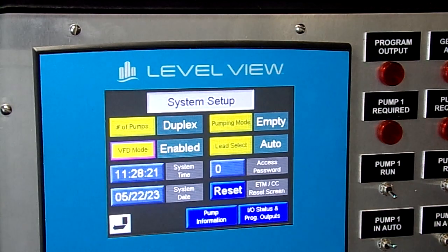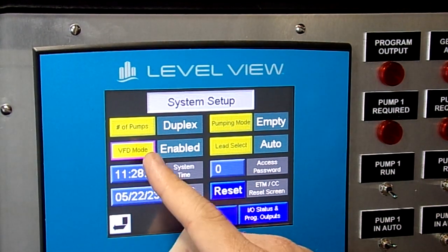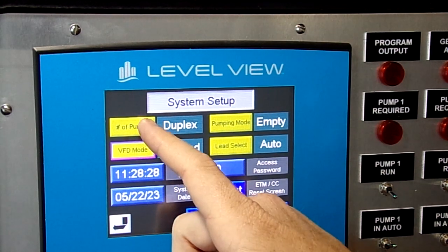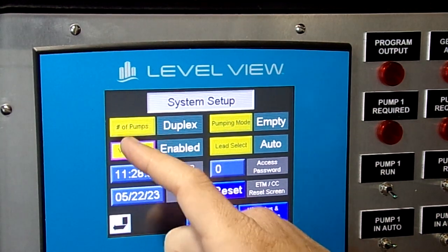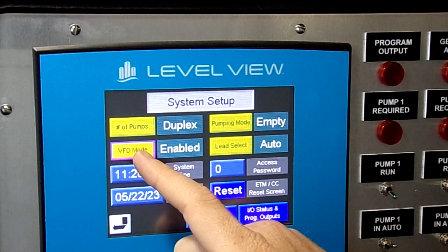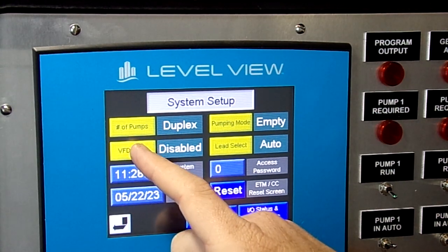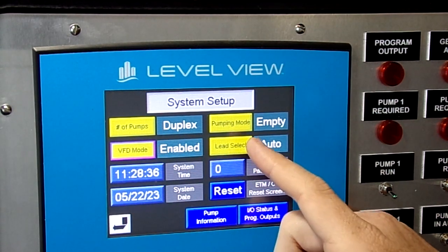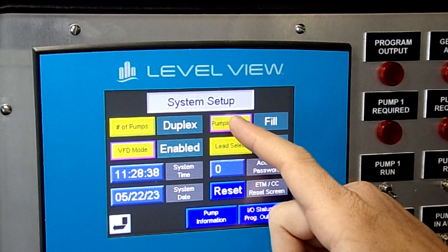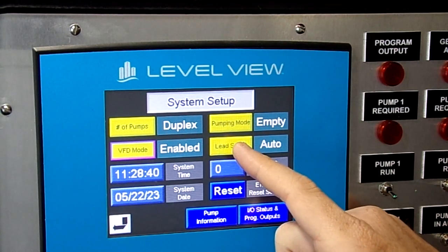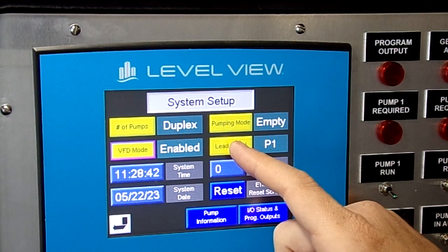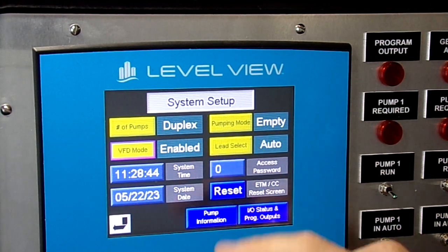The system has a multitude of different applications that it can be run for. So we have a duplex or a triplex. We also currently have this set up for VFDs that can be disabled or enabled. This station can be set up to empty or fill stations. And then we also have the ability to do lead select for auto, pump 1, or pump 2.